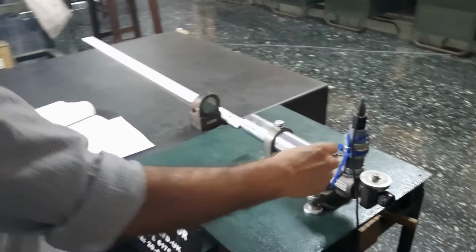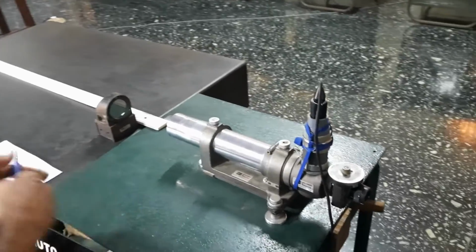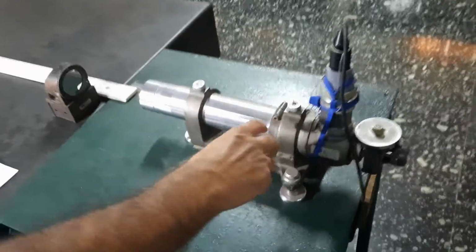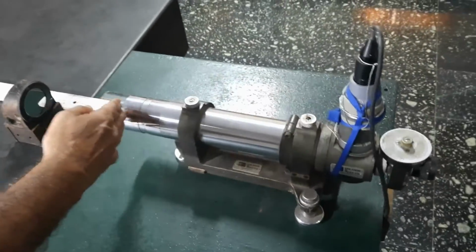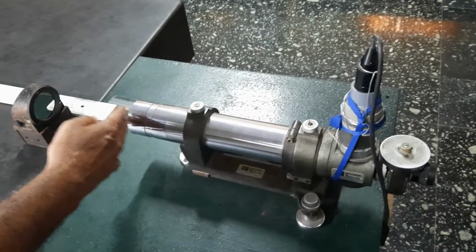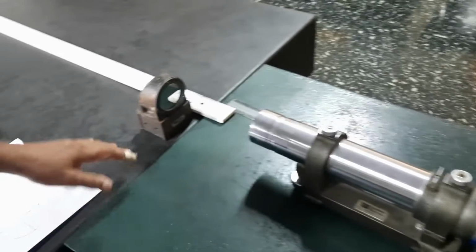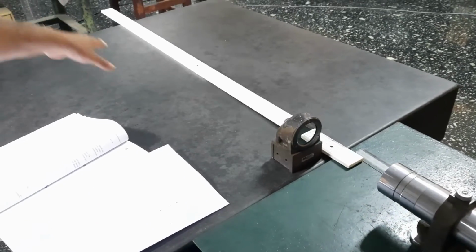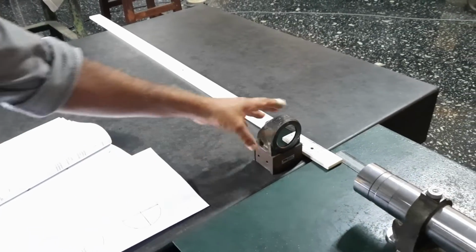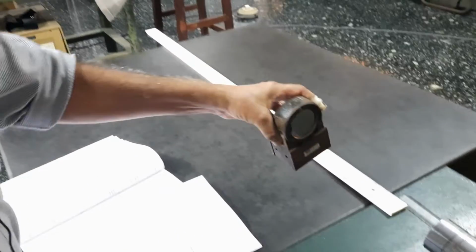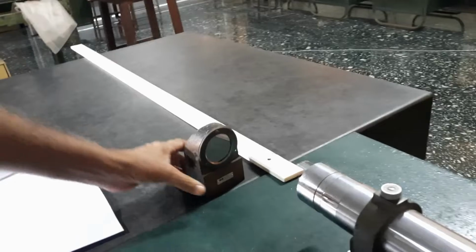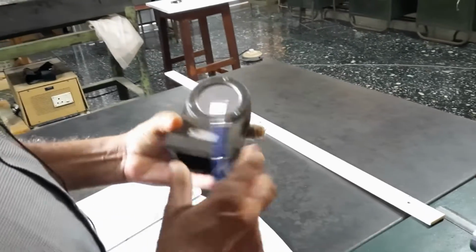The parts of the instrument: this is the collimator part, passing a parallel beam of light, and this light falls on the reflector. So this is the surface plate. We are going to find the straightness of the surface plate.